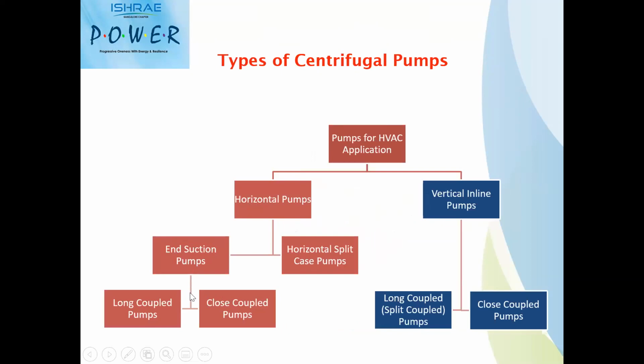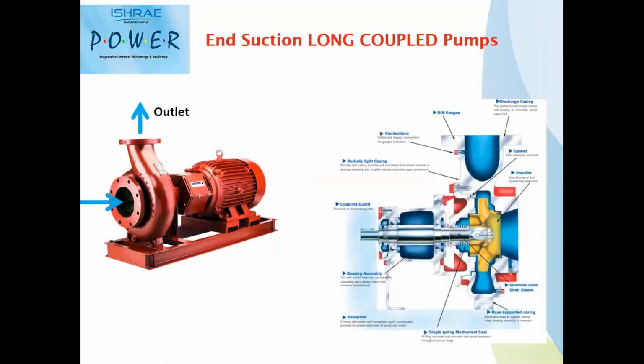And when it comes to end suction, again, we have long coupled as well as close coupled. Similarly, for vertical inline pumps, we again have long coupled pumps and close coupled pumps. I'll just quickly take you through the types of pumps with respect to their construction and features. This is a typical end suction pump, which is long coupled, where your pump and motor are connected through a coupling, which is mounted on a base plate. Here it is called a back pull out end suction pump because the suction of the pump is from one side and the discharge is on the top side. So this is a typical section.